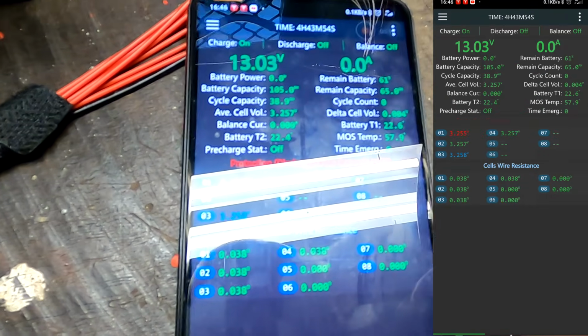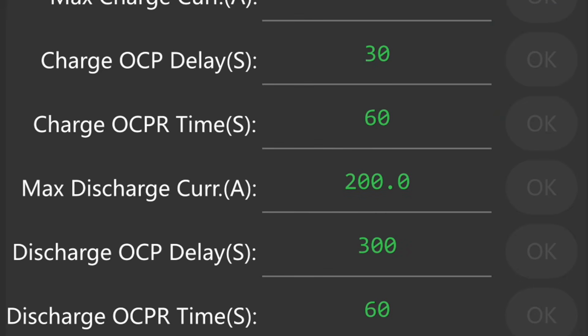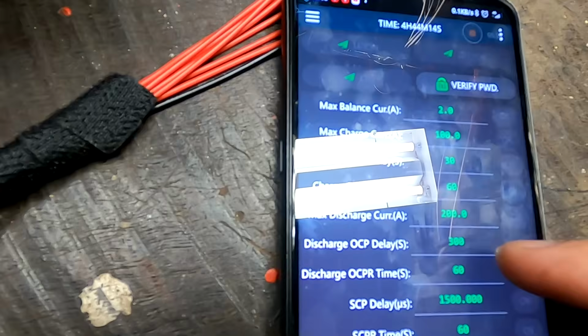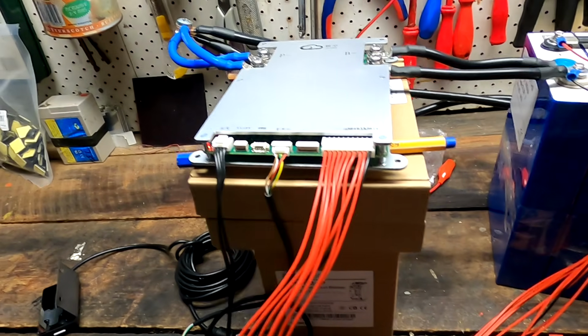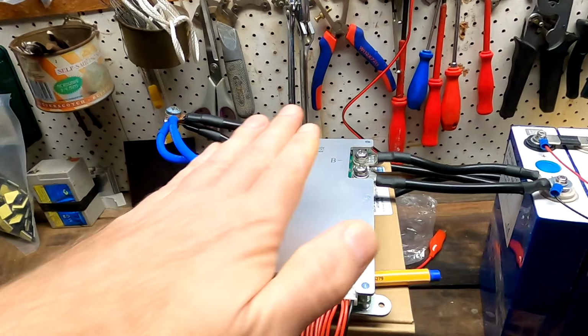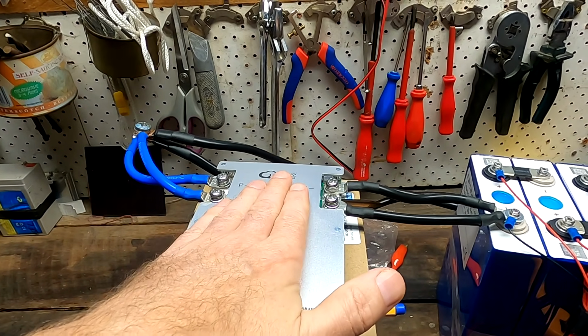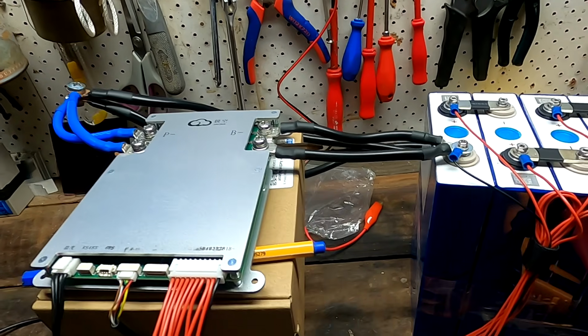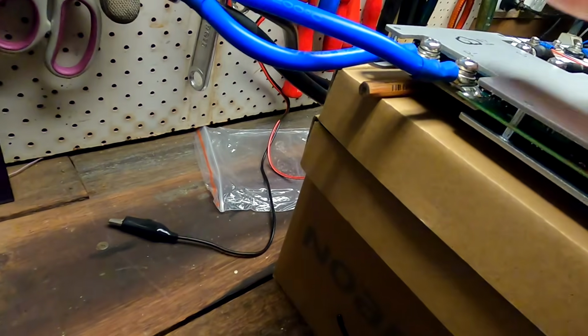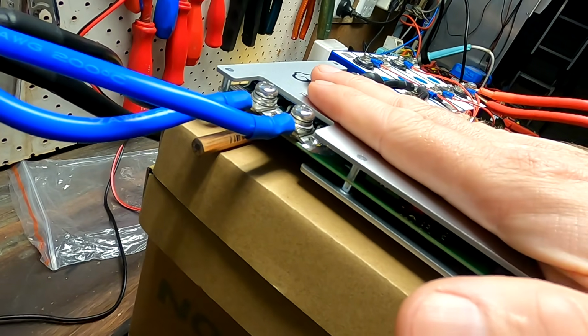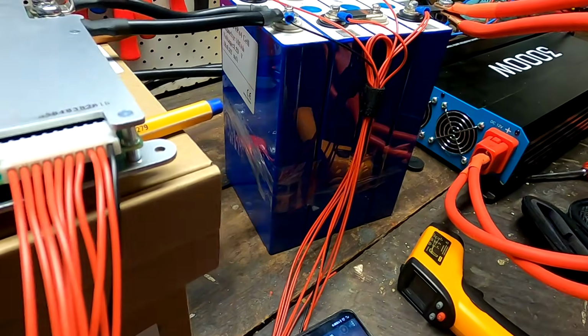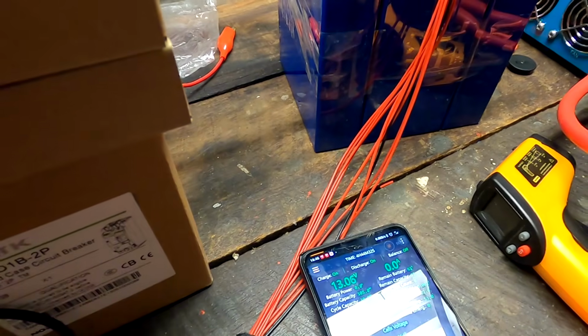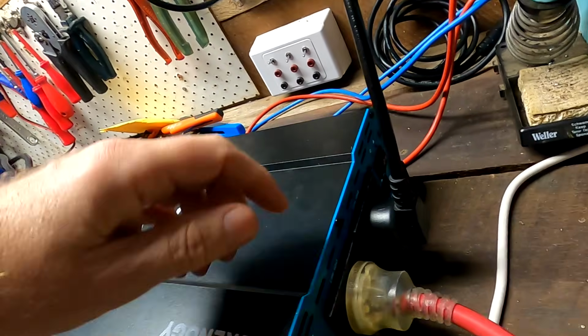Protection discharge overcurrent, yeah see, it set on 200 amps for 5 minutes or so, and we have actually pulled 203 amps all the time, and then the BMS turned off. So I probably have destroyed the BMS now, because the MOSFETs have turned off and got destroyed while disconnecting this high current. I would say I need a new BMS because the inverter has turned off, right?